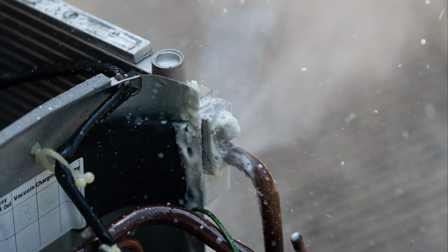Undercharged refrigerant levels increase the energy demands of the refrigeration system and can also be a direct source of greenhouse gas emissions. If the load across the chiller varies, variable speed drives can be installed to reduce energy usage. They work by modulating the work the compressor does, depending on the cooling load. Newer compressors with them already incorporated can be installed.